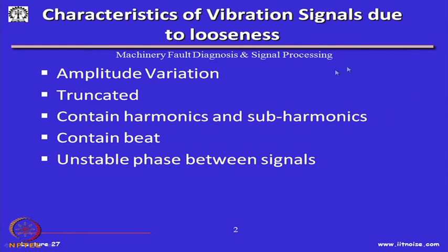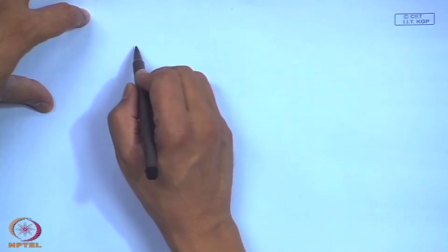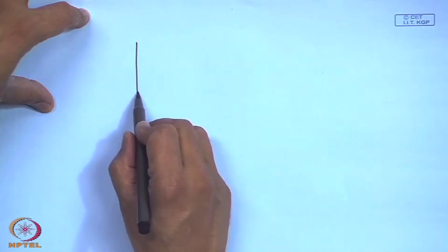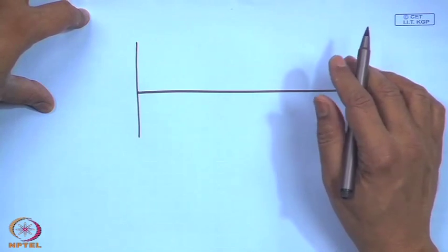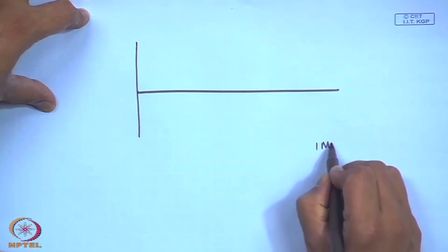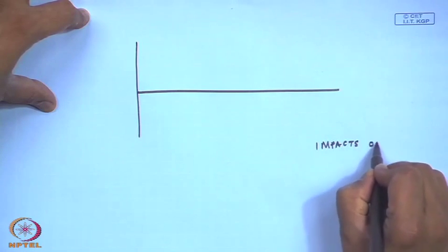The characteristics of vibration signals due to looseness include: significant amplitude variation, signals in the time domain that look truncated, harmonics and sub-harmonics, beating of signals, and unstable phase between signals. When things are loose, components fly around and hit against each other, producing a series of impacts.